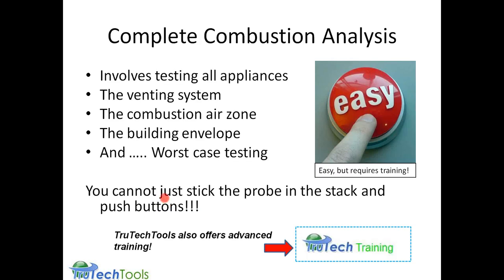A complete combustion analysis involves testing all the fuel burning appliances within a space or an envelope. It also involves testing the venting system, because air is so important to combustion, how much oxygen you get in the air that gets through to the combustion system. If the venting is affected, it could affect how much air is pulled through. It also involves the combustion air zone, to check if there is any spillage or any depressurization in the air zone, the building envelope, and worst case draft testing. So all these combine together to make a really complete combustion analysis.